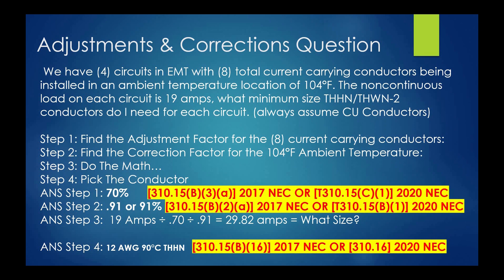So let's look at this question. We have four circuits — I'll assume these are two-wire circuits because it says a total of eight current-carrying conductors, so four circuits, two conductors each: one ungrounded and one grounded conductor. They're located in EMT, which is a tubing, not a conduit. Eight total current-carrying conductors installed in an ambient temperature location of 104 degrees Fahrenheit. The non-continuous load on each circuit is 19 amperes. The question asks: what is the minimum size THHN/THWN-2 conductor needed for each circuit?